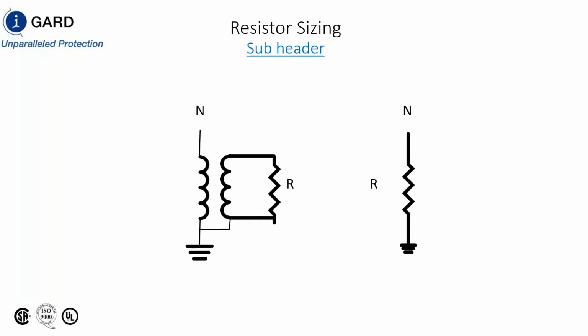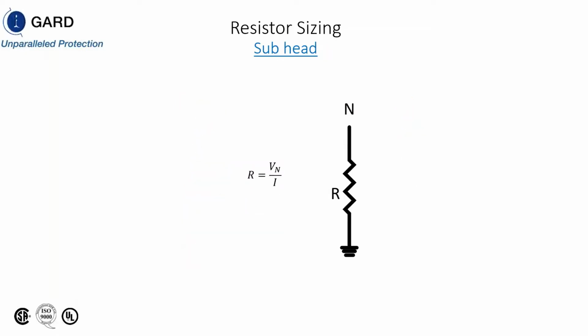So, a method of selecting resistor sizes. Obviously, if the neutral is available, we have this particular scheme. You can use a transformer coupled with a resistor, or just use a straight resistor. And if that's the case, the resistor is equal to the line to neutral voltage divided by the fault current that you want to limit the fault to. So if you had a 13.8 kV system and you wanted to limit the fault current to 5 or 10 amps, that's an 800 ohm resistor.